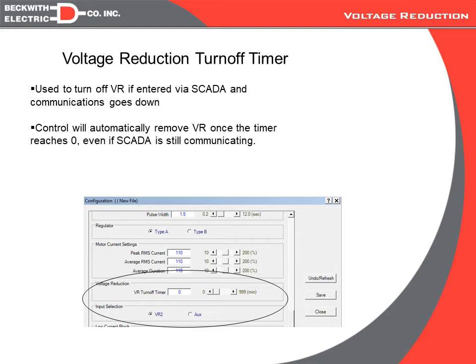So for instance, if it's set for 15 minutes, the first time I enter reduction, it'll start the timer counting down. If I do not send another reduction command to keep it in reduction before the 15 minutes expires, it will automatically come out of reduction on its own. If I want it to stay in reduction for an additional 15 minutes, I'll have to reissue that command just prior to the timer expiring and get another 15 minutes.